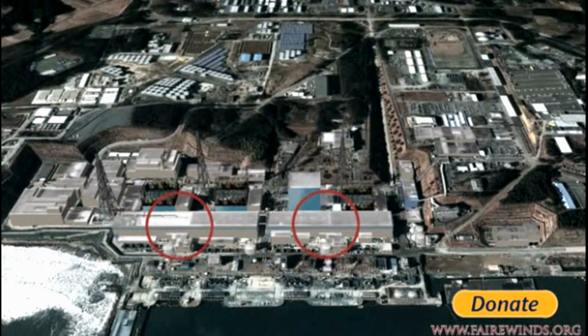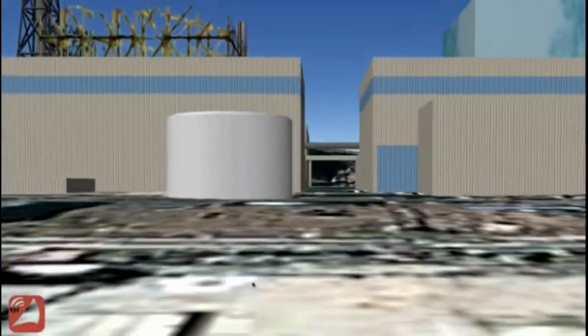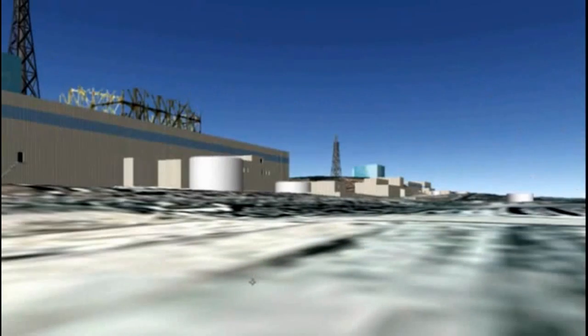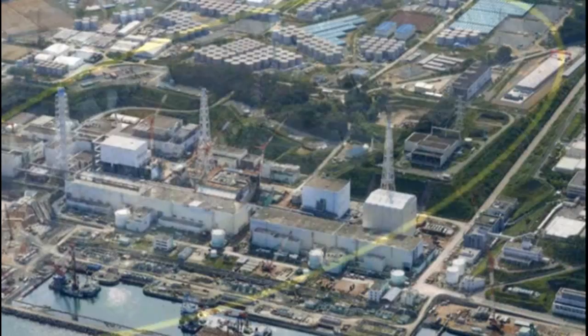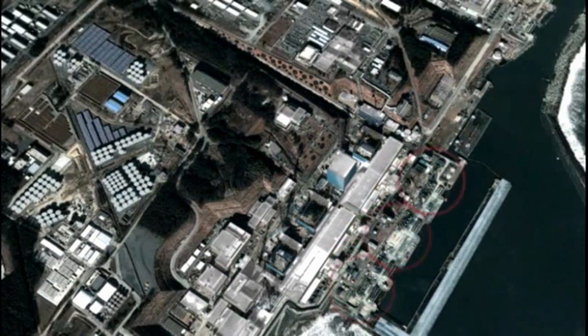There's a long row of turbine buildings along the water. While impressive, there's not much going on inside them from a nuclear safety standpoint, though they do have basements flooded with radioactive waste. Beyond those is rubble along the waterline — that's where the cooling pumps were, which all failed as a result of the tsunami. Even if the diesels had not been flooded, they would have failed anyway because all of that rubble along the coast.